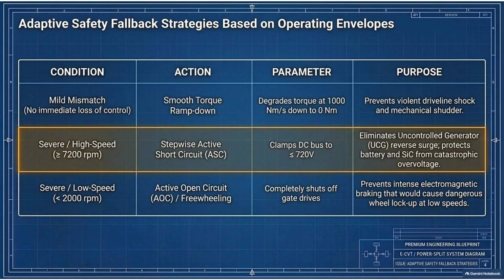Yeah. One core, the doer, does all the heavy computational lifting: the field-oriented control, the active damping, all the high-frequency switching. And the checker core? The checker core is physically isolated and runs a completely different, highly simplified mathematical model based on unbreakable laws of physics, like stator flux conservation. So it avoids common cause failures by not even trying to do the complex math. Right. It just looks at whether the doer's requested output mathematically violates the absolute physical limits of the DC bus. And if it does? If the checker catches the doer trying to do something unsafe, it doesn't even try to correct the math. It completely bypasses the main core, triggers a hardware interrupt, and directly kills the power to the inverters in under 100 microseconds.